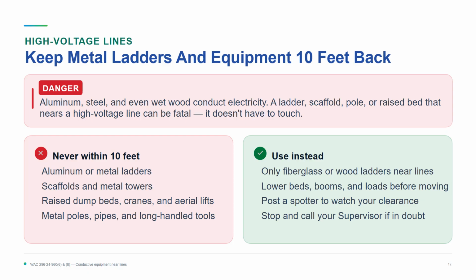Anything that conducts: aluminum and metal ladders, scaffolds, raised dump beds, cranes, aerial lifts, metal poles, and long tools, stays at least 10 feet from a high voltage line. It doesn't need to touch. Electricity can arc across the gap. When you are near lines, use only fiberglass or wood ladders, lower your loads before moving, and post a spotter.